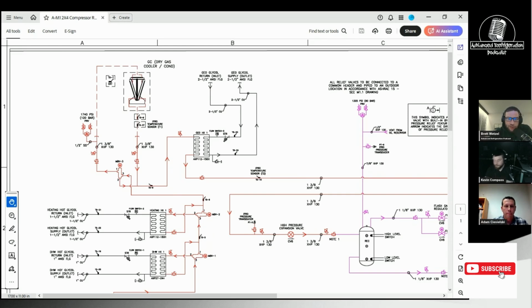Oh, I remember what it was. We were talking about the split for a second. Adam, you said you were concerned that when you put the unit back into operation, you might get a fluctuation. So you could use some sort of bipolar stepper to essentially pressurize it, like Walmart does with their HFC racks. Right before it would come out of split, you would repressurize the split side of the condenser to raise it up, so there wasn't so much thermal shock and it wouldn't go erratic. Because we all know with CO2, one little change over here ripples down the line. So being able to take a little bit of that gas and pressurize the split side lets you control that.